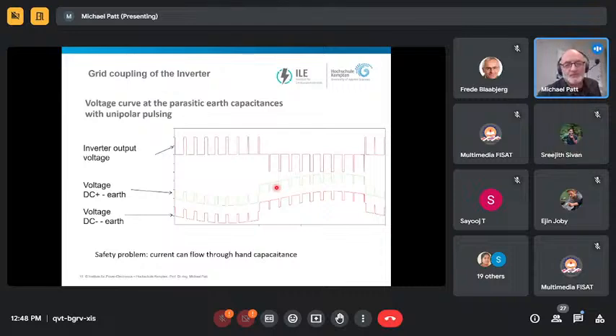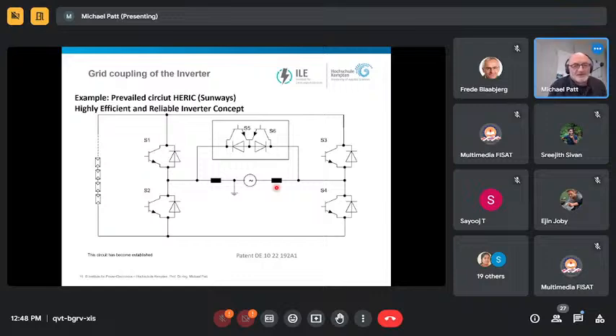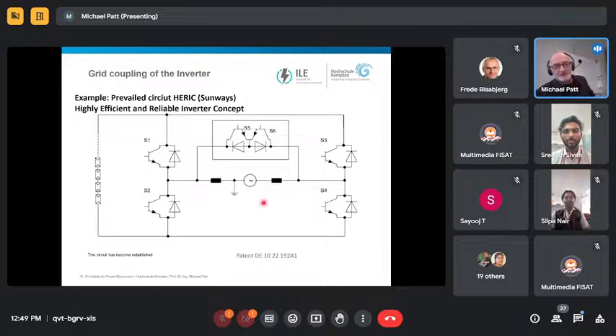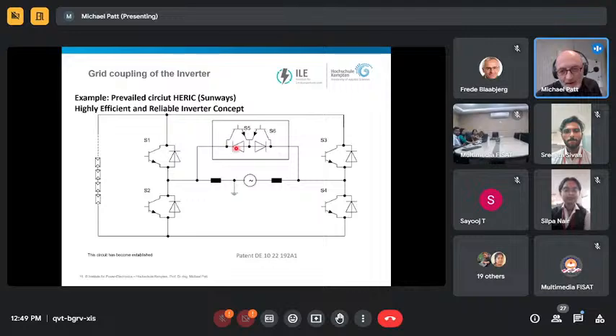We need other circuits. One is called HERIC, which stands for Highly Efficient and Reliable Inverter Concept. The trick behind the circuit is that the free-running path, which is normally sent to the low side or the high side, can now flow through this bidirectional switching element instead. This circuit has become established, and you can achieve very high efficiencies, up to 99%. It was invented by Heribert Schmidt from the Fraunhofer Institute in Freiburg.